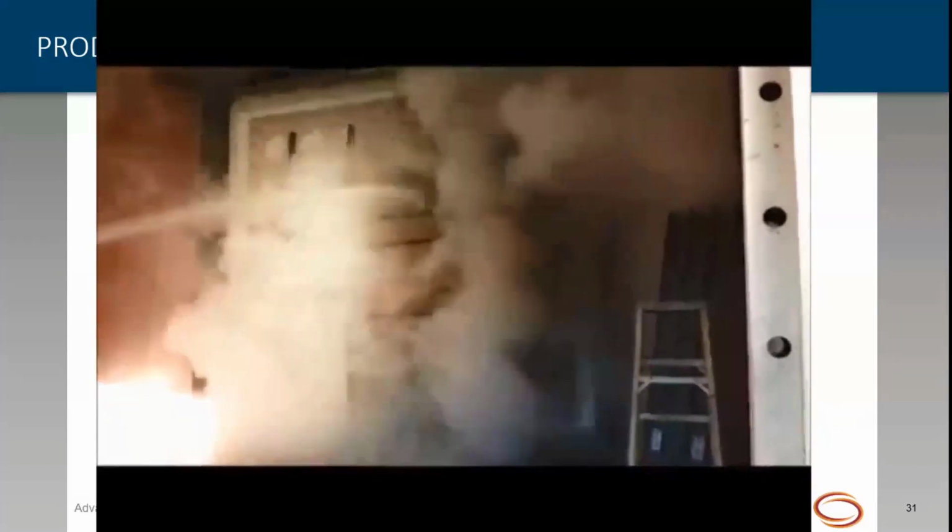Now, this is not to mimic a firefighter fighting a fire. All that's being done is the mechanical security of the actual product. It's just making sure that at the end, when it cools, especially if it cools rapidly, it's going to stay intact at the end of that 2 hours. So that's what the water hose stream test is. Very, very cool to watch. Creates a huge mess, but a lot of people have never seen this, so I thought it would be interesting to show you.